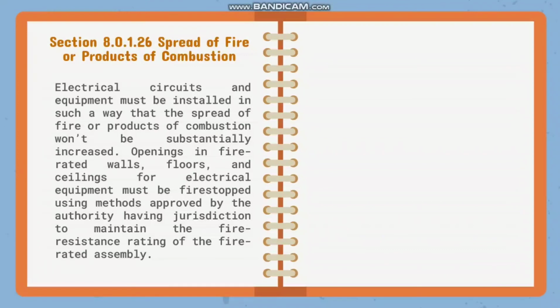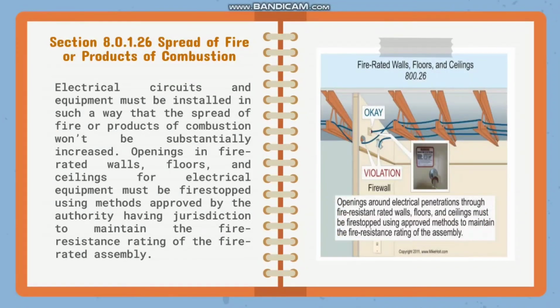8.0.1.26, spread of fire or products of combustion. So, as you can see po dito sa illustration, yung communication cables po ay nag-penetrate or dumaan through fire-rated walls. At hindi lahat po ng openings ay naka-seal o may fire stop. So, it is a violation po sa section 8.0.1.26. So, according po dun sa code, yung openings po kung saan dadaan po yung communication cables, communication raceways, and cable routing assemblies through fire-resistant rated walls ay dapat naka-seal or meron dapat fire stop.